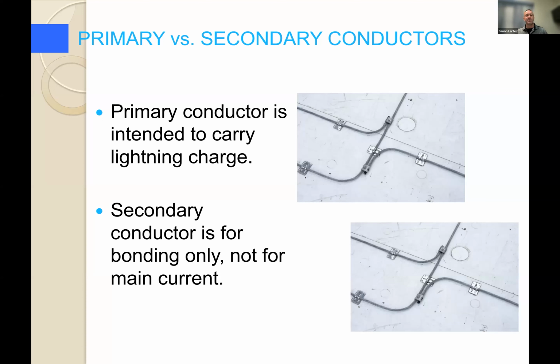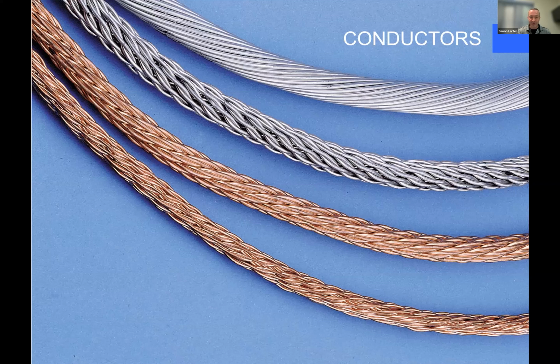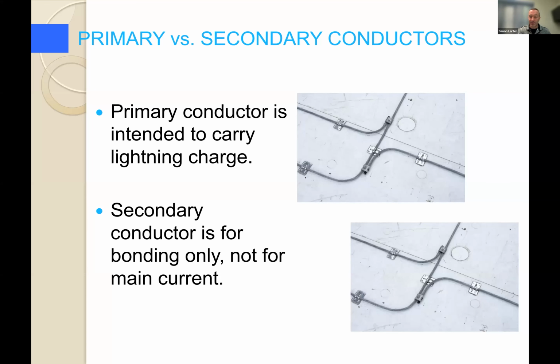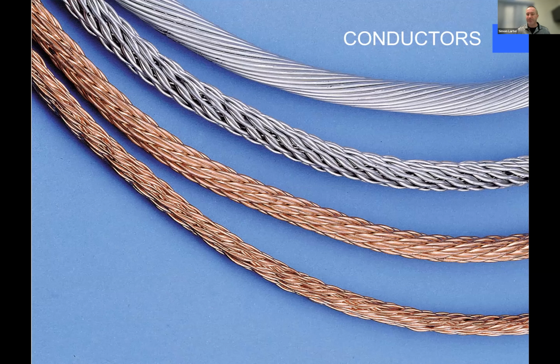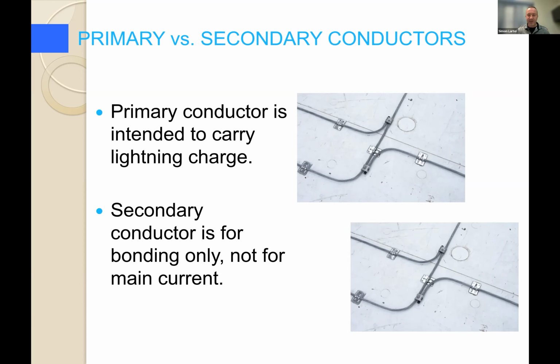Primary versus secondary conductors. Primary conductor is intended to carry a lightning charge. That's all of these. These are all intended to carry a lightning charge. Secondary conductor, however, that's for secondary bonding. We would use that with a metal body of inductance, not conductance, not one that's subject to a direct strike and needs protection on it. Inductance, something that we could potentially have a flashover to. That's what secondary conductor is for. It's much smaller. It's about half the size of the class 1 cabling there. We use that just for interconnections, equipotential bonding. Lightning current is not supposed to flow on that. So it's a primary conductor, it's a main size, it's going to carry a lightning charge. That's its intended use. Secondary conductor, not supposed to be carrying charge, just an equipotential bond. And that's for those metal bodies of inductance, not conductance.